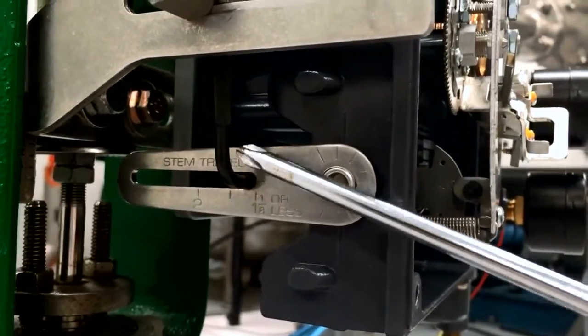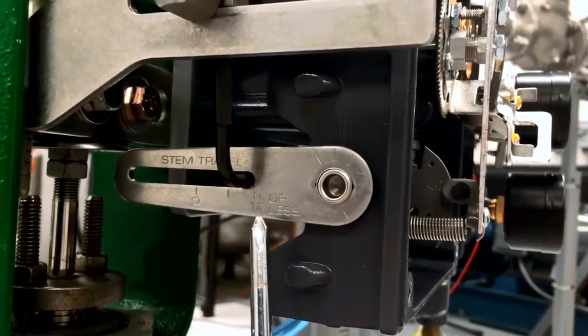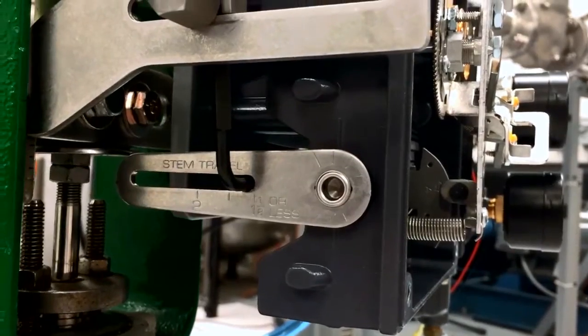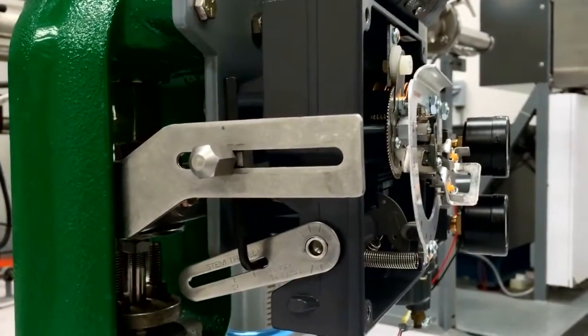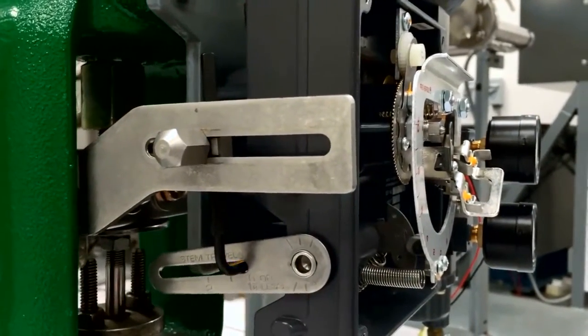The travel pin should be positioned based on the valve maximum travel. In this case it is 3/4 inches and we position it at 1 1/8 or less. From here we will fully stroke the valve from close to open, ensuring that the arm does not rotate out of the range inscribed on the arm.